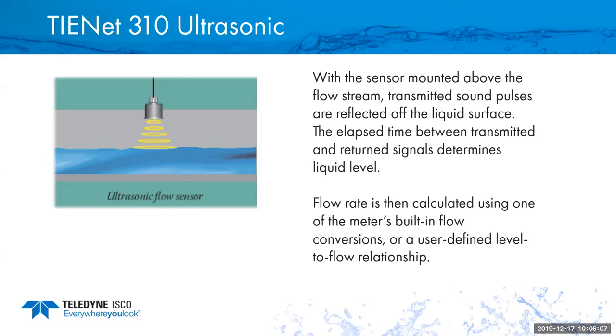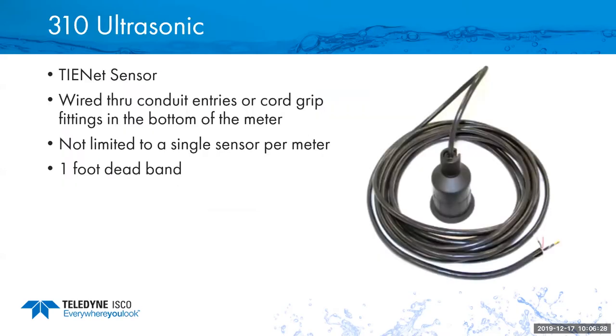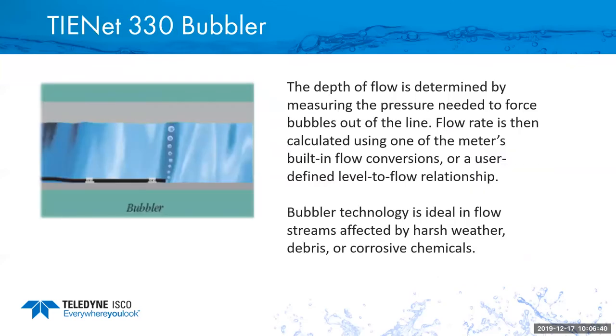Now with ultrasonic sensors, you typically don't want to deal with something that has a lot of steam or foam or maybe a lot of wind, which can influence the readings of the ultrasonic sensor. In that case, you would usually look for some other technology to measure the flow. So with the TIENet sensor, we would wire it into the signature flow meter with the wires there. It has a 1 foot dead band, which means you would always want it to be 1 foot above your deepest flow you ever get.